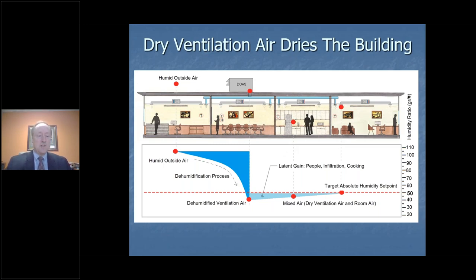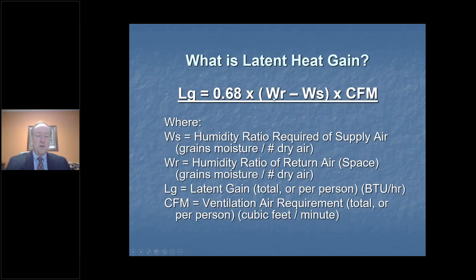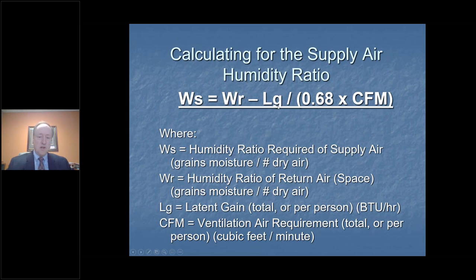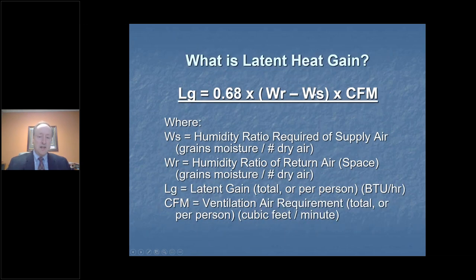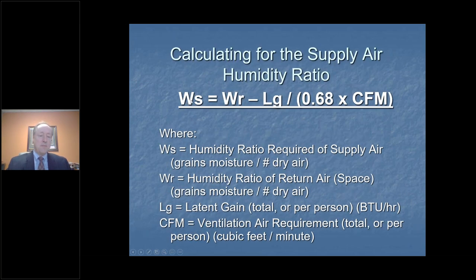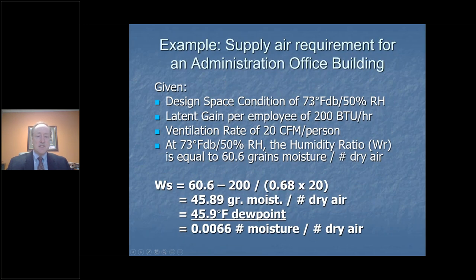So this is the formula I showed you earlier. W is the humidity ratio, so I've already spoken to that. I know everything in here except for what the humidity ratio is of the supply air that I need to deliver into the space. So solving for that particular value, this is what the formula would look like.